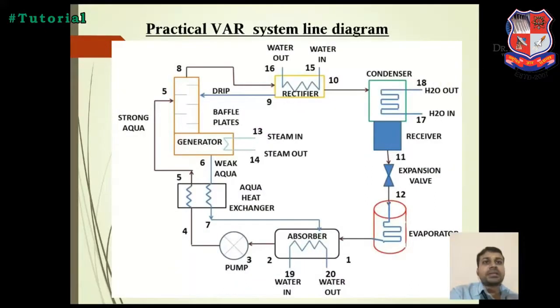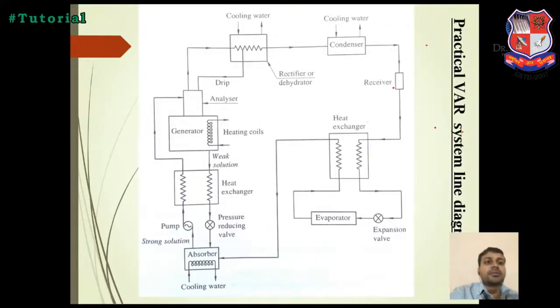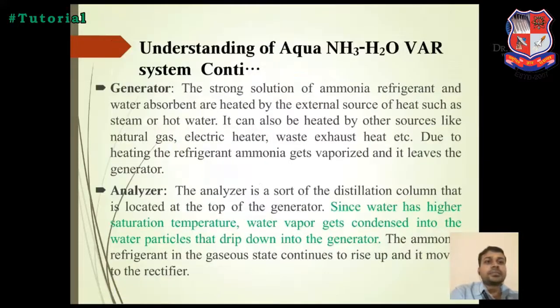There is another practical VAR system line diagram. It will show that above this PPT, in this slide, is another diagram. Understanding of the aqua NH3-H2O system. The generator holds a strong solution of ammonia refrigerant and water absorber, heated by an external source such as steam or hot water. We give heat in the generator and it creates a vapor of ammonia and H2O.